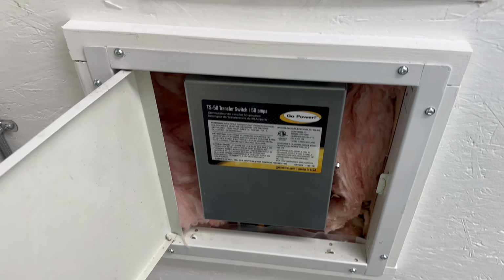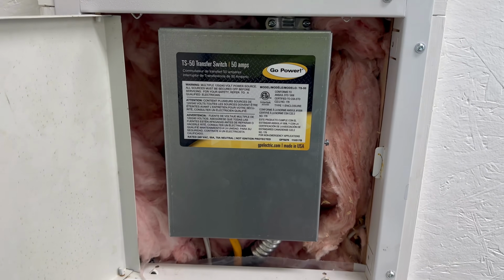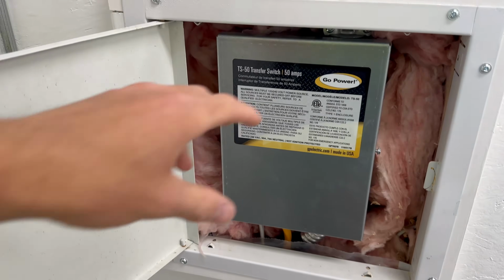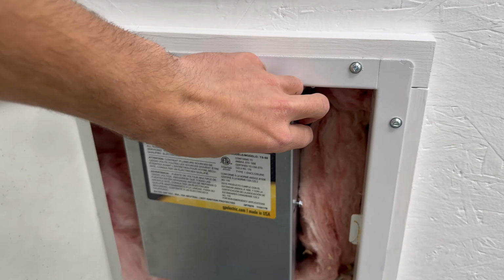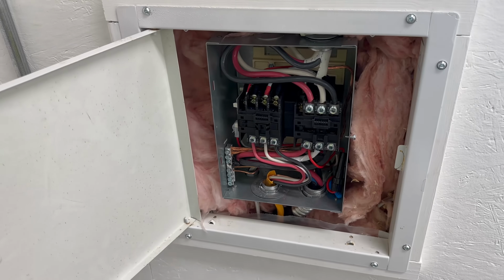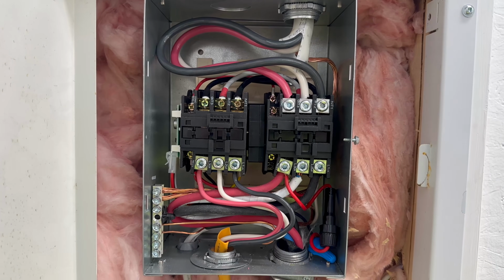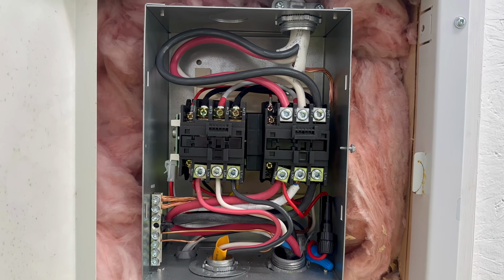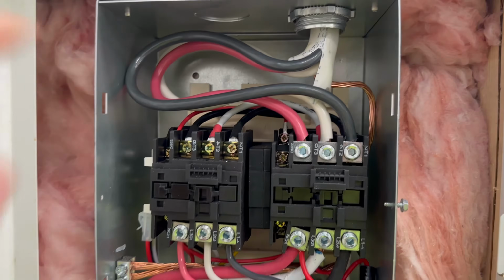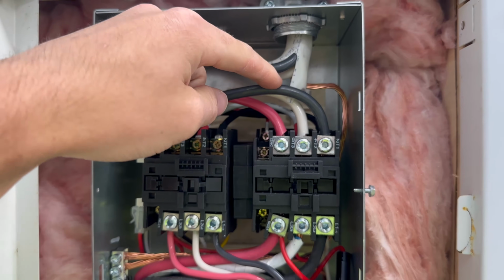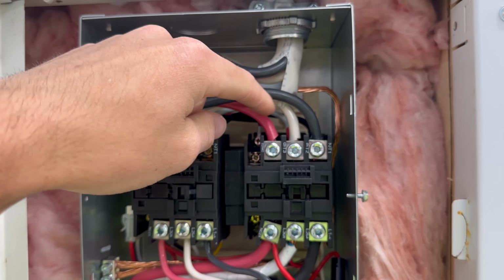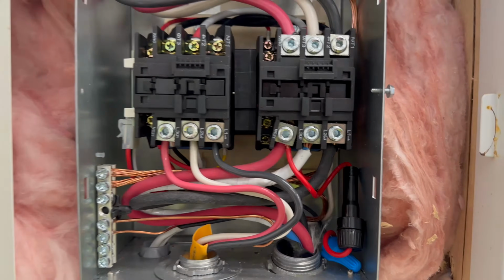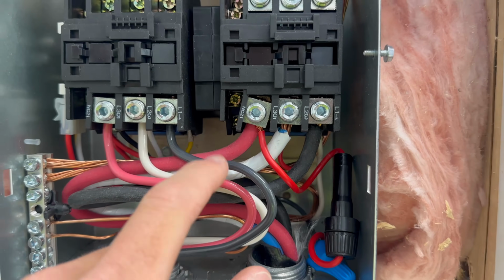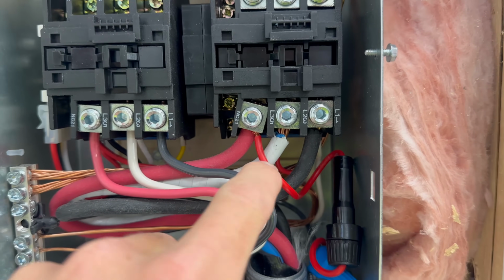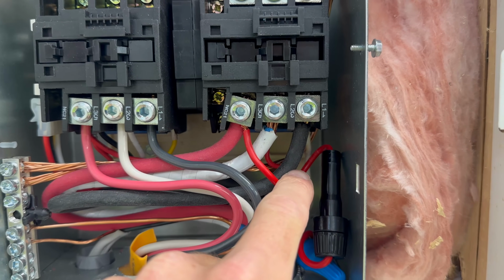Once in the initial cover, we have the actual transfer switch right here, which we can take the cover off of this guy as well. And in here you have the actual transfer switch itself, which may look complicated, though it's pretty simple. Right here is the load side of the transfer switch. This is your one hot, your neutral, and your other hot. Then coming in right here, you have your power from BC Hydro, your hot, your neutral, and your other hot.